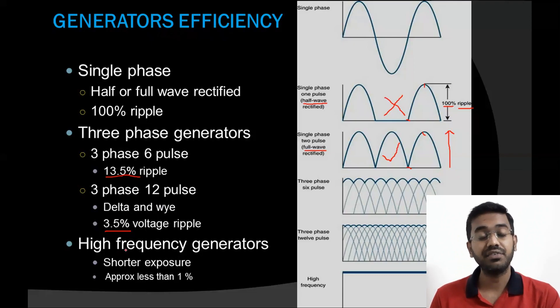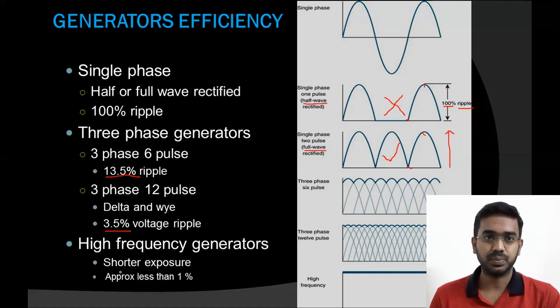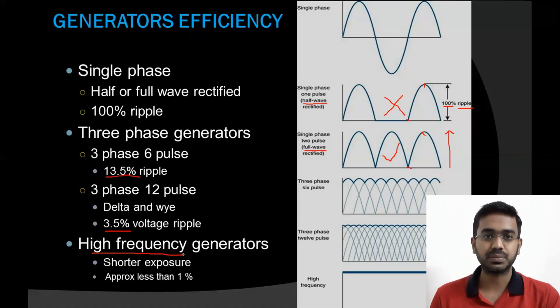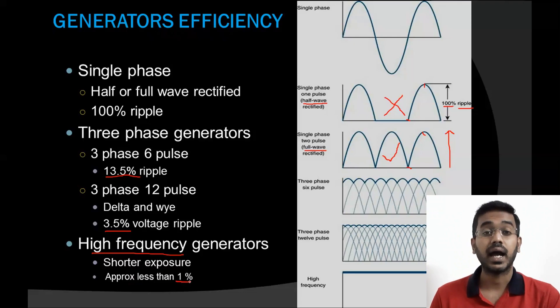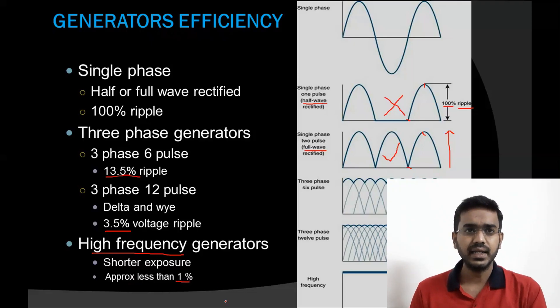Next, the high-frequency generator. In most modern-day equipment, we use high-frequency generators because they have shorter exposure times, the ripple is approximately less than 1%, and the size of the equipment is also smaller. If you want to know about generator efficiency in detail, just comment below and I will make a separate video on this topic.